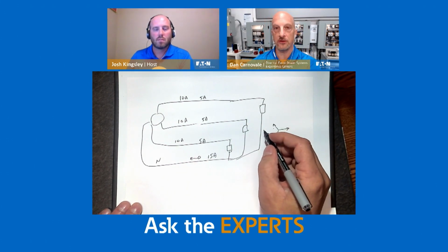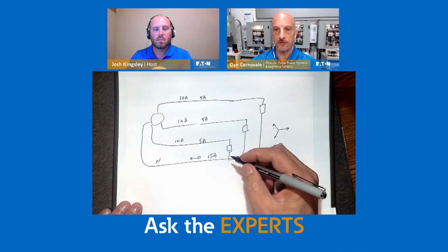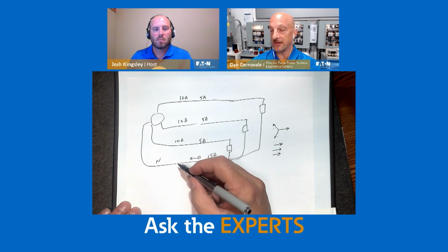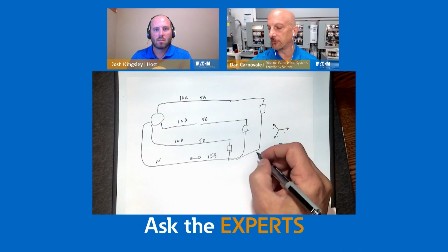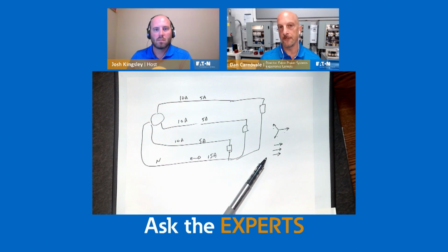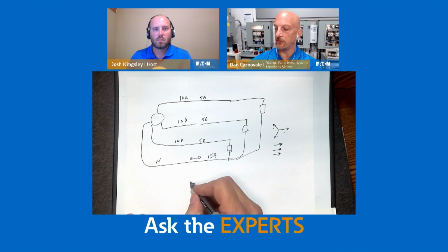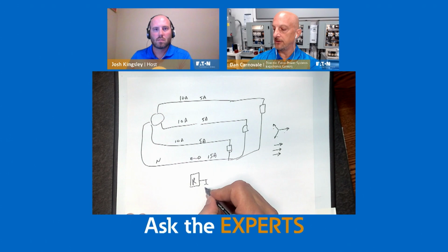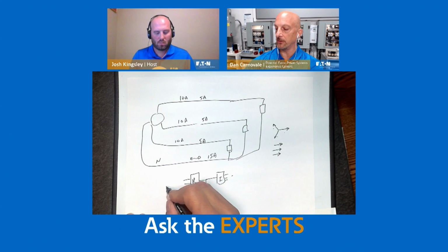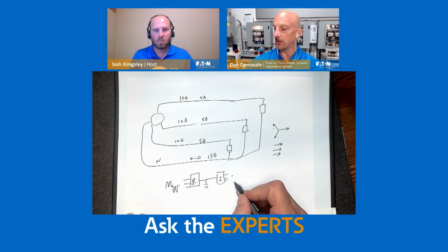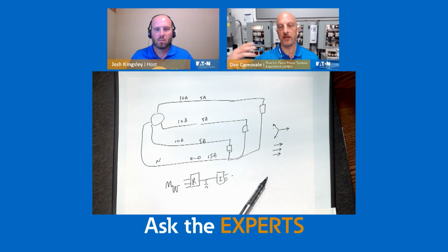Now, when you look at how things go, what you're referencing is a medium voltage system and a 480 volt system that doesn't have a neutral. So in this case, we're not talking about those low frequency, in this case third harmonic, zero sequence harmonics. What you're talking about, I think, is some of the higher frequency harmonics. And those can sometimes come from the outputs of VFDs, the pulse width modulated output. We usually don't think about harmonics coming from the output of the drive. The drive is a rectifier, DC bus with a capacitor, and an inverter. And the pulse width modulation on this output, that high frequency stuff, sometimes I've seen, if the input current looks like that double hump current that I drew earlier, the output current can have some 39th harmonic, like really high order harmonics.